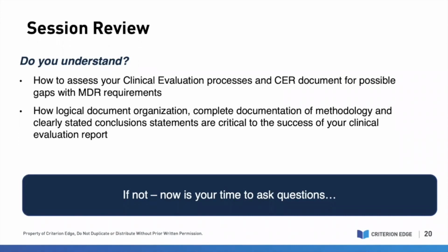How many literature databases do you normally use for your literature searches, and which ones would you recommend most? In our experience, with the CERs that we've written for different types of manufacturers, from cardiac, orthopedic, on and on, from many different viewpoints, Embase and Medline have always been accepted, and there have been no questions that have come back from either the client or ultimately the notified body about using those.